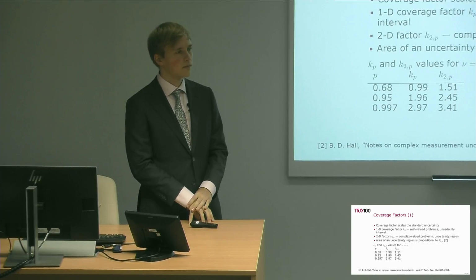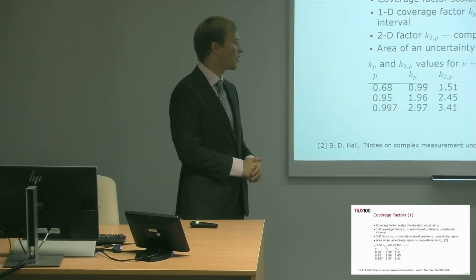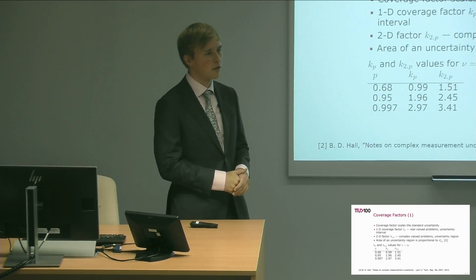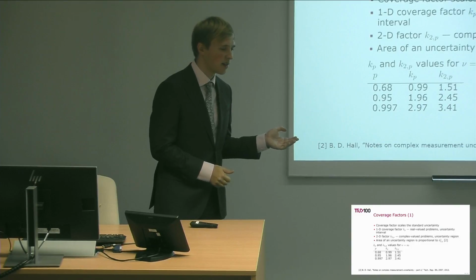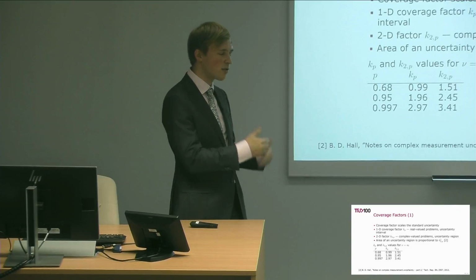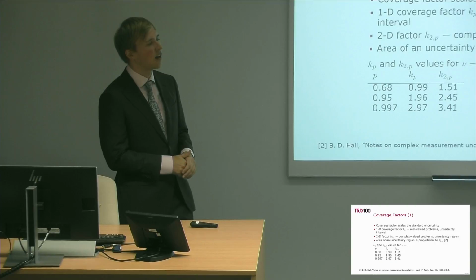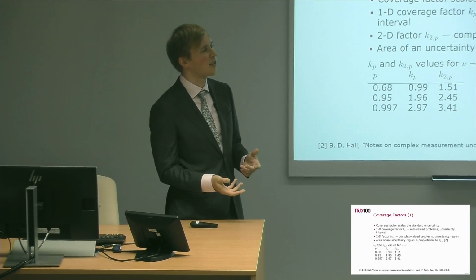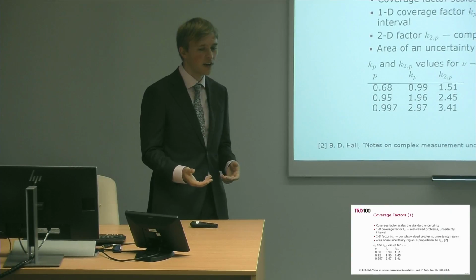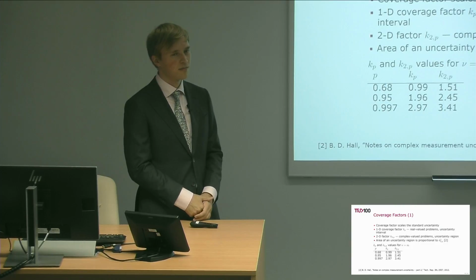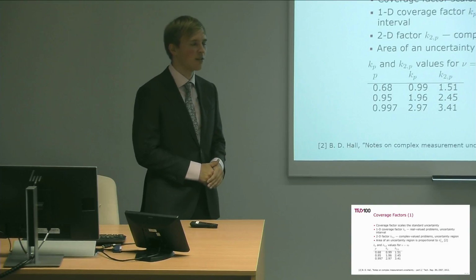Because in your conclusion you say, well, if more accurate estimates of line parameters are needed, either calibration or replacement of instrument transformers would be required. If this was the goal, then yes. But practically, as of today... Well, it depends, because resistance is one of the parameters, but the uncertainties of other line parameters are smaller. For example, the monitoring of corona losses, or the components of losses—both Joule and corona losses—is inherently still dependent on the same estimation principle, also using the estimate of line parameters in calculating the loss component.